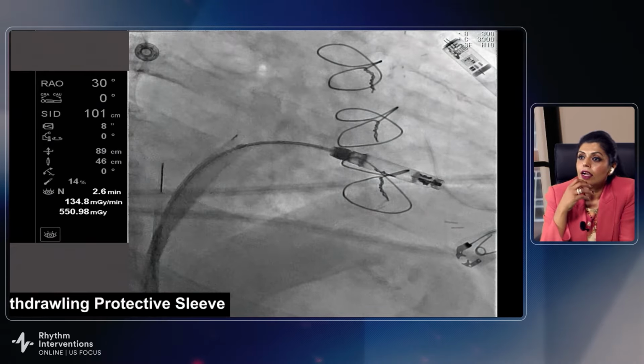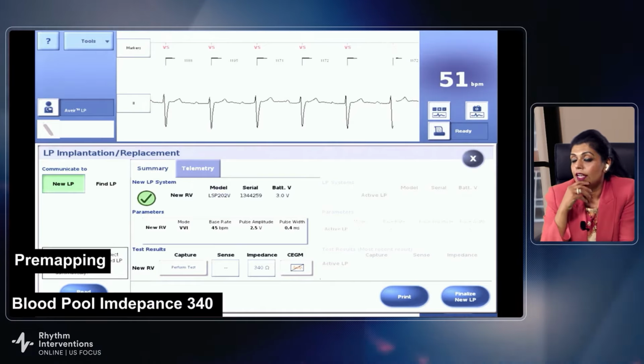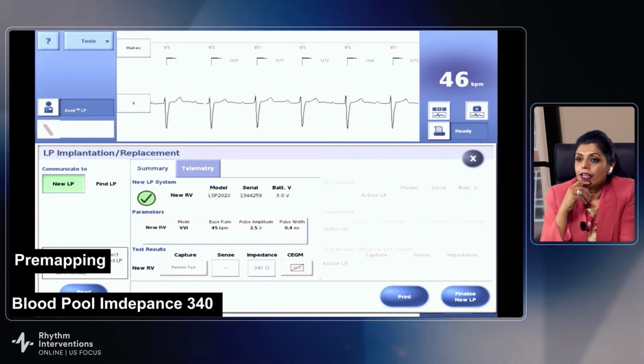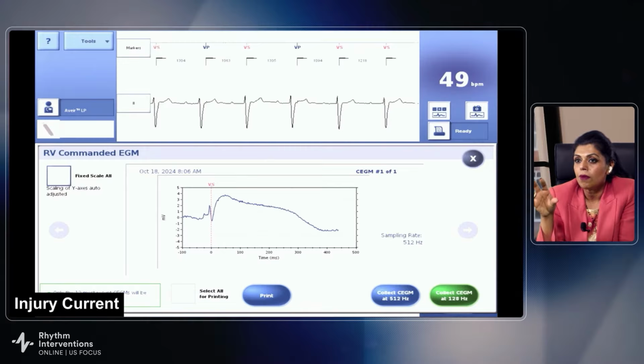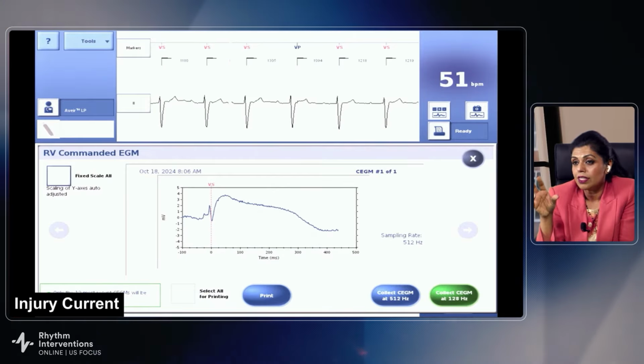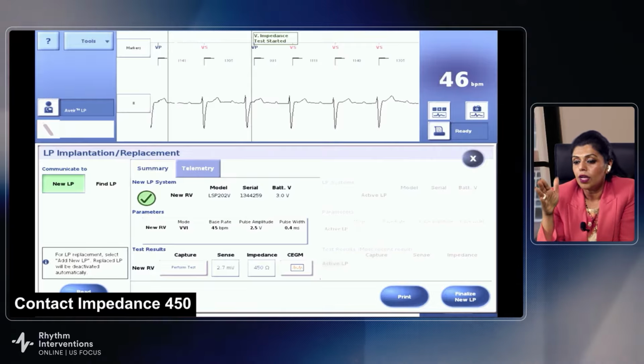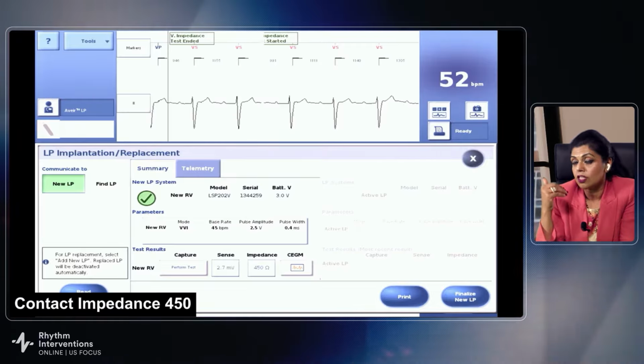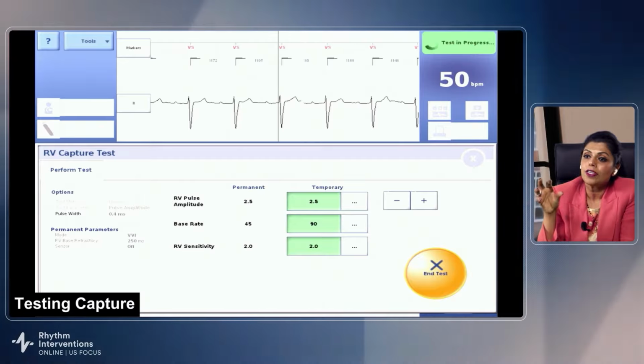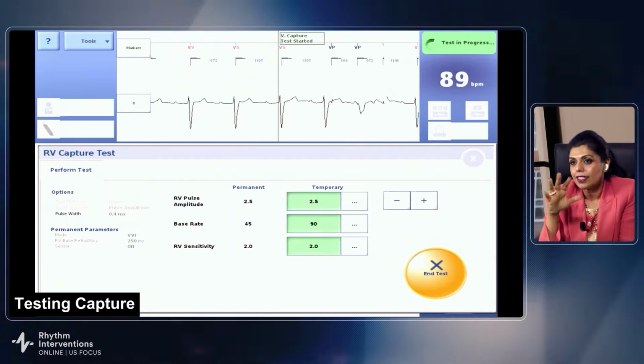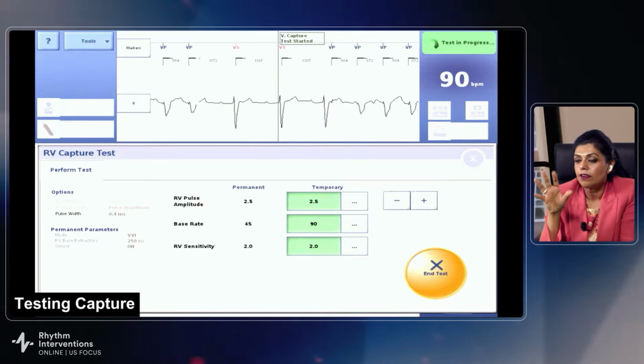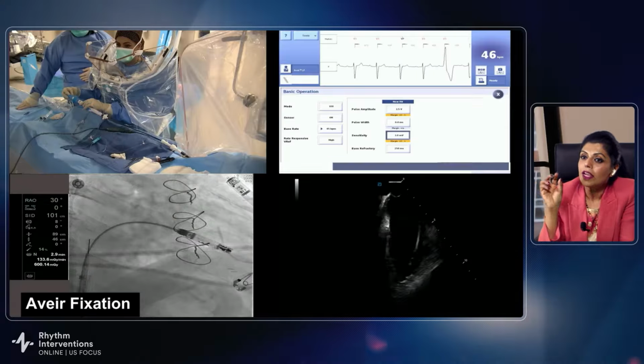I will say that I have put this device in other sites in the right ventricle, and because of this capability of pre-mapping, which is what I'm doing right now, we actually check a blood pool impedance when we are initially unsheathed in the right atrium, and then we're looking for a contact impedance of at least, I like somewhere between 400 to 500 range, and that tells me that I've got contact.